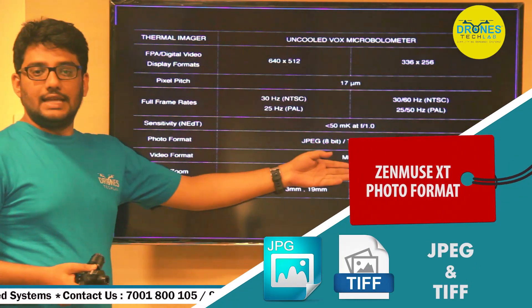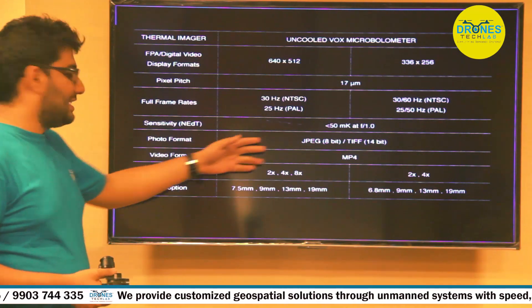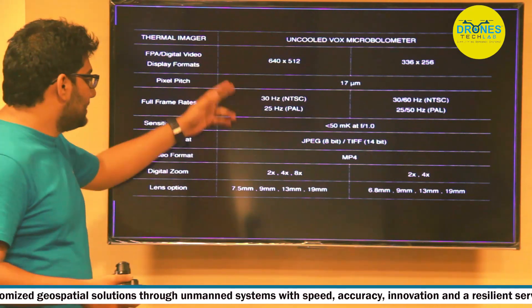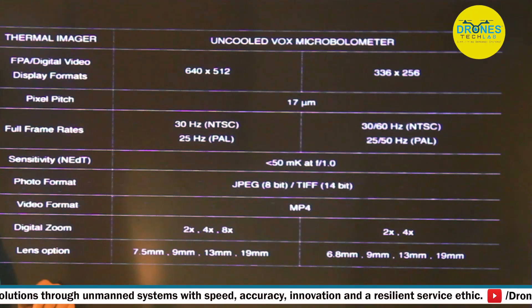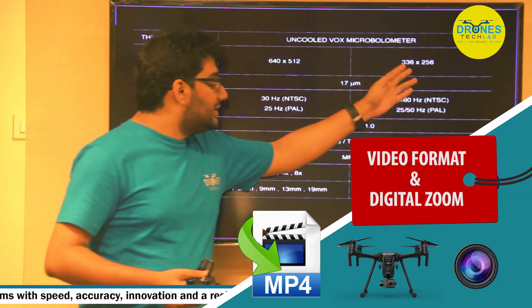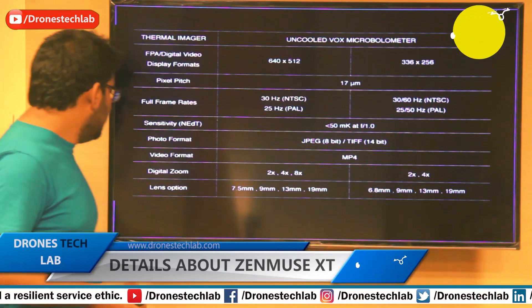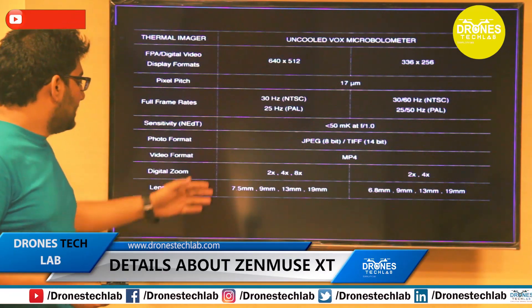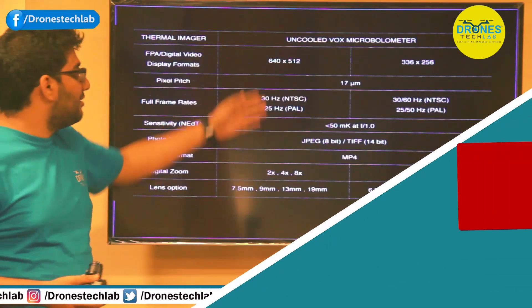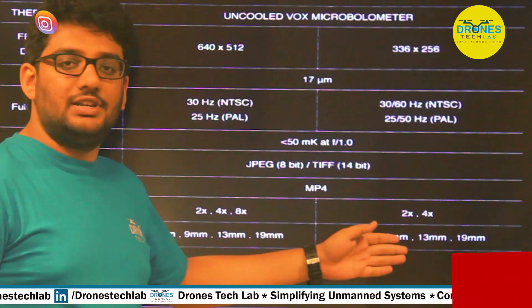The photo format comes in two types: JPEG (8-bit) and TIFF (14-bit). The video format is MP4. The key difference between the two sensor formats lies in digital zoom: the 640×512 format has a digital zoom of up to 8x, whereas the 336×256 format has a digital zoom of only 2x and 4x. Regarding lens options, the 640×512 format supports 7.5mm, 9mm, 13mm, and 19mm, while the 336×256 format does not include the 7.5mm option but offers 6.8mm, 9mm, 13mm, and 19mm lenses.